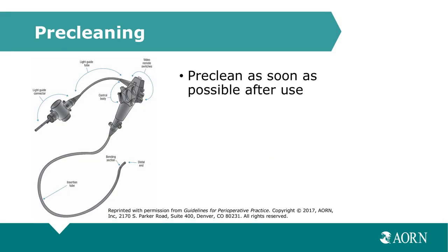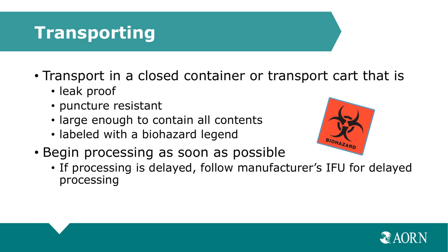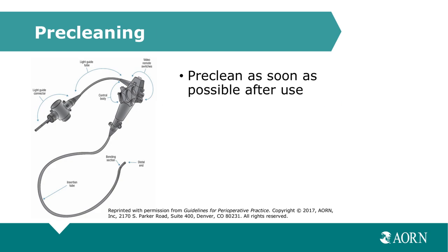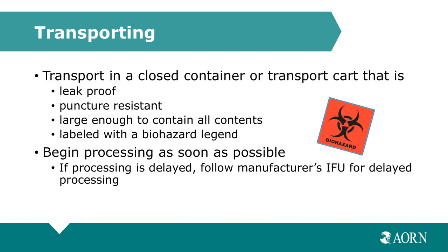The first step in processing a flexible endoscope is to pre-clean the device at the point of use. Pre-cleaning should occur as soon as possible after the endoscope is removed from the patient or the procedure is completed and before organic material has had an opportunity to dry on the surface or in the channels of the endoscope. After pre-cleaning at the point of use, the contaminated endoscope and its accessories should be transported to the endoscopy processing room. Contaminated endoscopes must be transported to the decontamination area in a closed container or a closed transport cart.